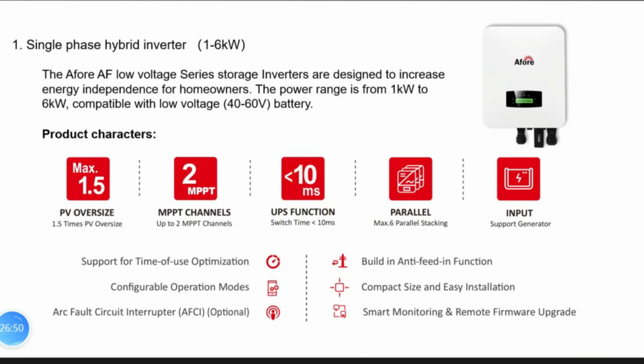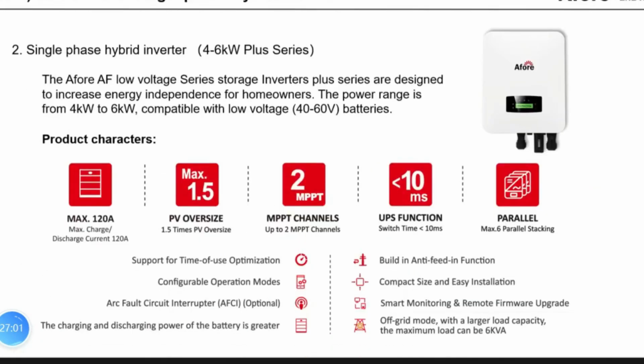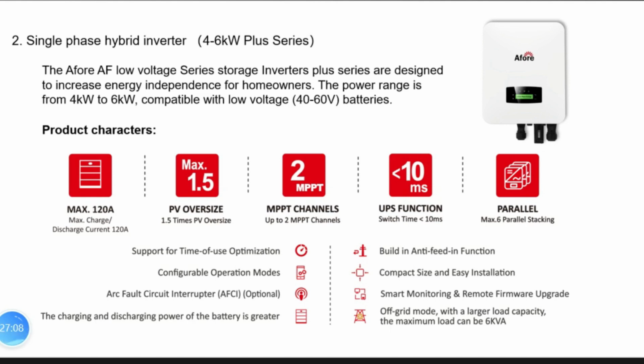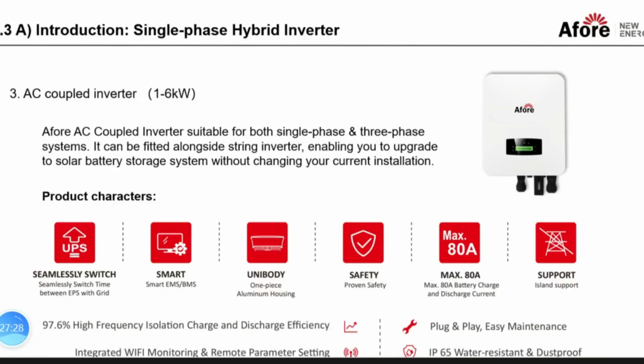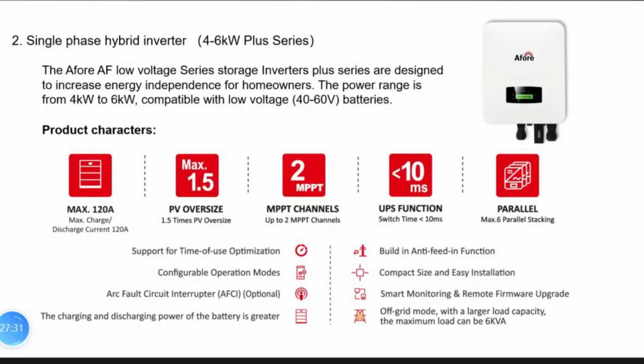Also, all versions have UPS level switching time. From on-grid mode to off-grid mode, it's within 10 milliseconds. For some systems, if the system capacity is bigger than 6K, the inverters can be connected in parallel. The maximum connection is 6 units right now. The normal inverter and the AC coupled one share the same menu structure and operation modes, like time of use, self-use, etc. For the detailed operation modes, I will provide more information in the later pages.